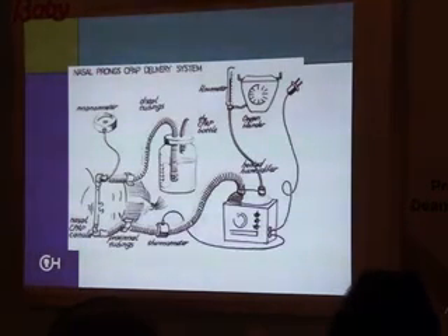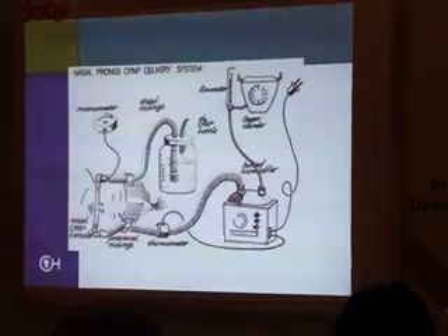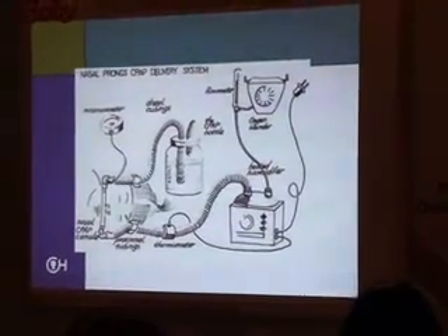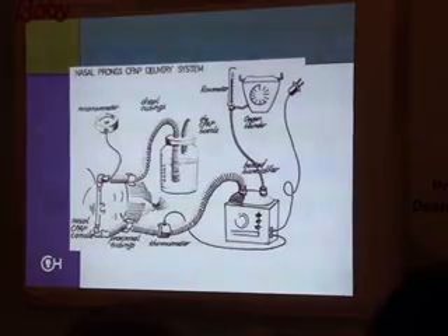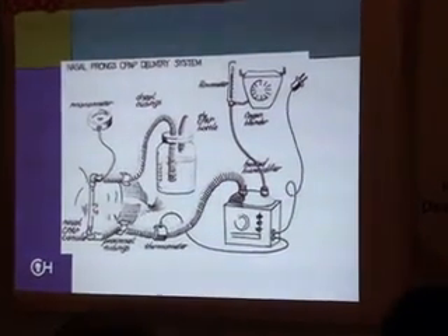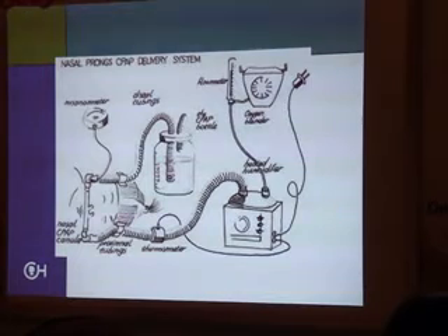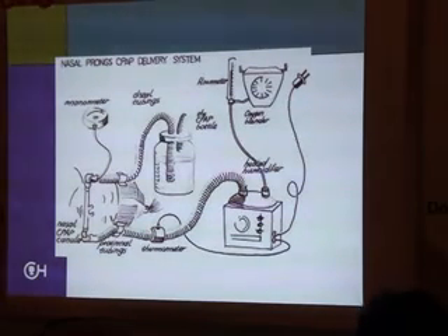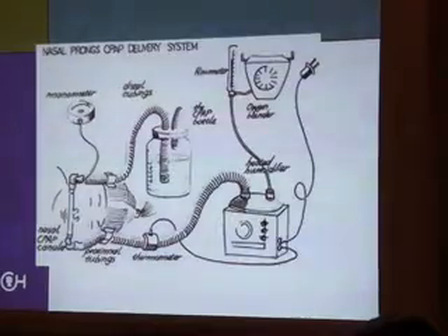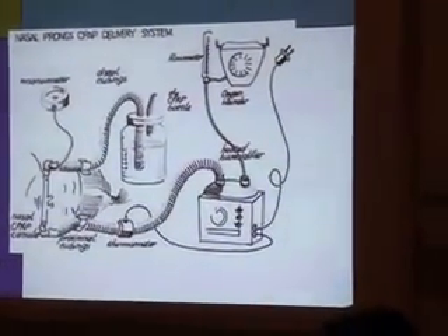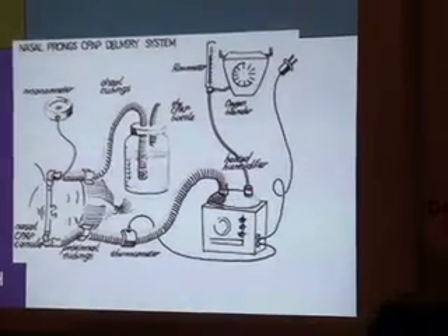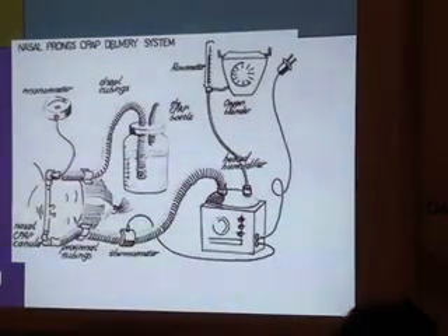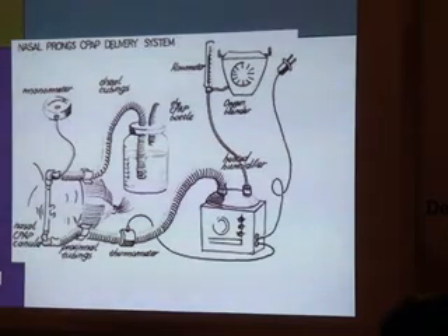This is kind of the picture of our old school CPAP, which a lot of people still use. You're setting your flow rate here with a blender going into your heated chamber that goes through and essentially this continuous flow that goes past the nares that the infant is breathing in and out against to the exhalation of your water column that's set. You have your centimeters of water pressure on the side. And oftentimes there's a readout that you can put on for an external manometer, but that's an additional piece, and a lot of the hospitals don't even use those. But no alarms. You can put some external alarm boxes on. Again, it's something else you have to get, not necessarily made for the system. So then we're starting to be engineers. And that's not our primary focus. And what we say in the U.S. is we're jerry-rigging things. We're adding things on, putting stuff that hasn't necessarily been made or been tested together.